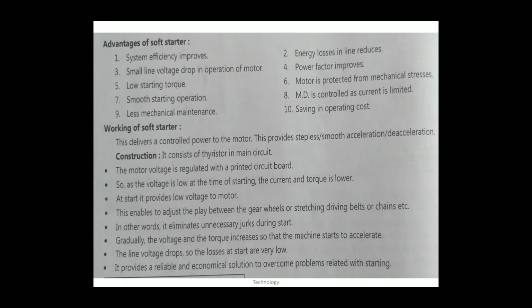This delivers controlled power to the motor. This provides stepless or smooth acceleration or deceleration. In construction, it consists of a thyristor in the main circuit. The motor voltage is regulated with a printed circuit board. As the voltage is low at the time of starting, the current and torque are lower. At start, it provides low voltage to the motor.